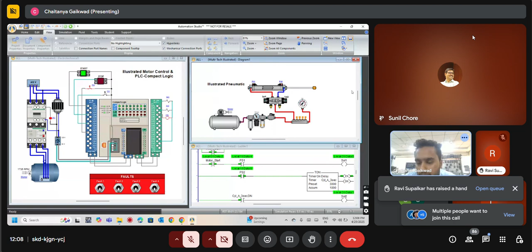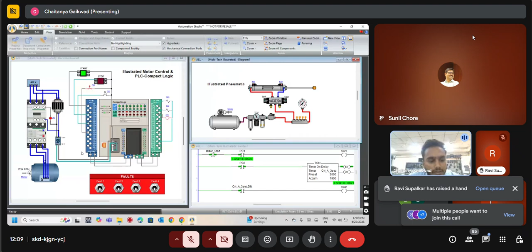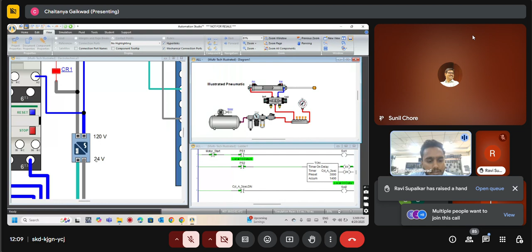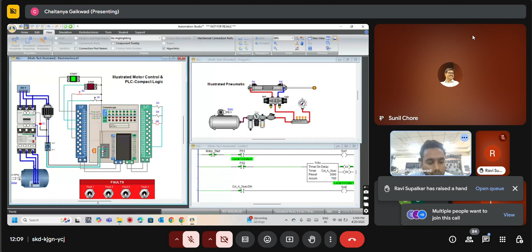And then all the actual hard wiring of the PLC - what is my power, what is my control wiring, what is my power wiring, how the sourcing part and sinking part work, how the PLC's power system operates. My PLC works on a 24-volt DC source, so I need an AC to DC converter, which converts 120 volts AC to 24-volt DC. Then it gets energized. Then I'm taking inputs and outputs, different coils, relays, and how they are being connected.